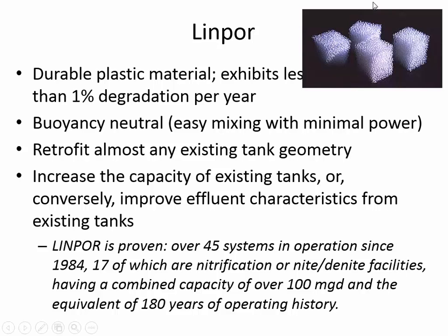So here's a look at the Linpor cubes, and what sets them apart from some other media that could be introduced is that they're pretty durable. Like they break down less than 1% per year. One of the problems with plastic is that if it's set in the sun, it gets brittle and can break down just from UV exposure. And so I think part of the research they put into Linpor is trying to make it so that it's resistant to exposure from UV rays, because a lot of aeration basins are just out in the open. They're not covered or shaded at all.